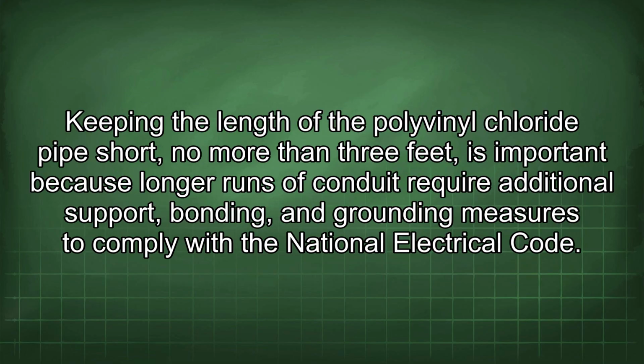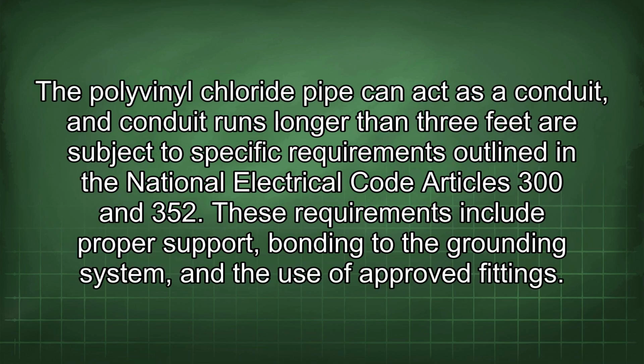Keeping the length of the polyvinyl chloride pipe short, no more than 3 feet, is important because longer runs of conduit require additional support, bonding, and grounding measures to comply with the National Electrical Code. The polyvinyl chloride pipe can act as a conduit, and conduit runs longer than 3 feet are subject to specific requirements outlined in the National Electrical Code Articles 300 and 352.